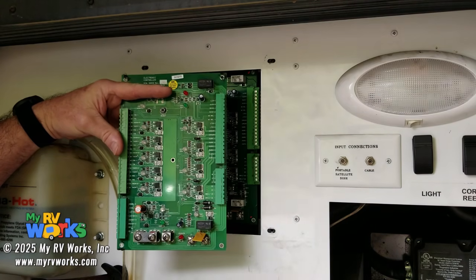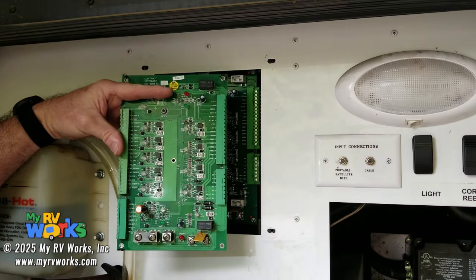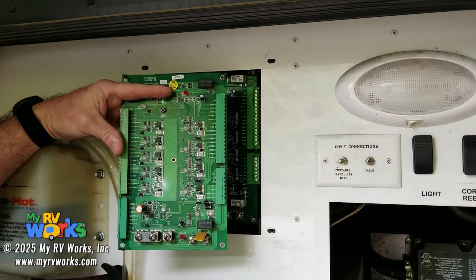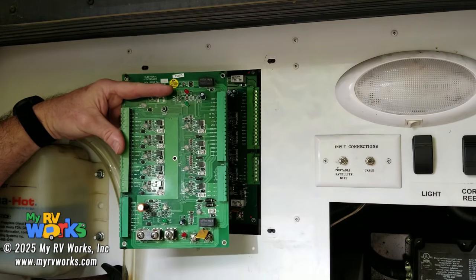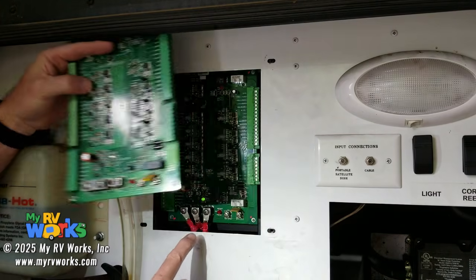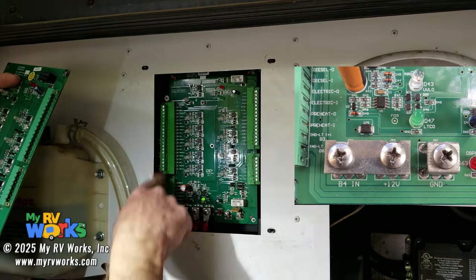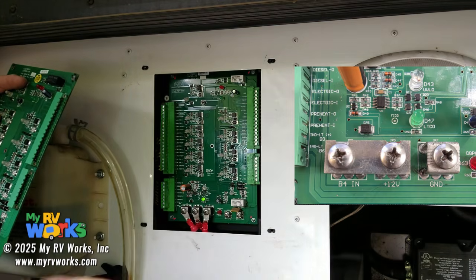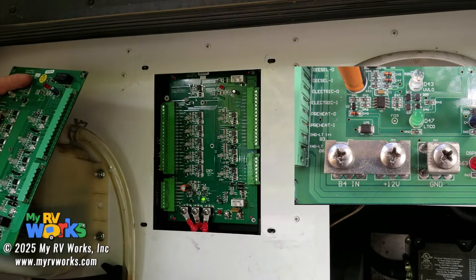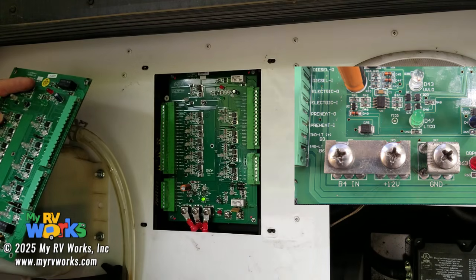This AquaHot, when it turns itself off normally and naturally, needs a 3-minute post-purge, it needs 3 minutes to cool itself down. But if you hit the battery disconnect and take power away from this lug right here, this thing shuts down, and all your cozy heaters turn off and everything just shuts down, denying the AquaHot of its 3 minutes post-purge. Not very healthy, not very happy.